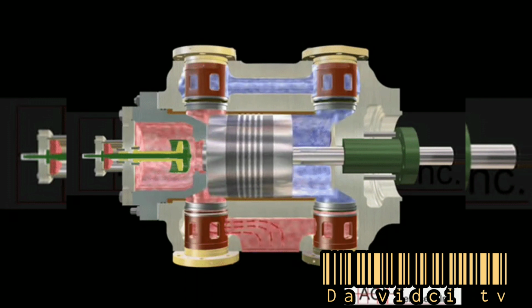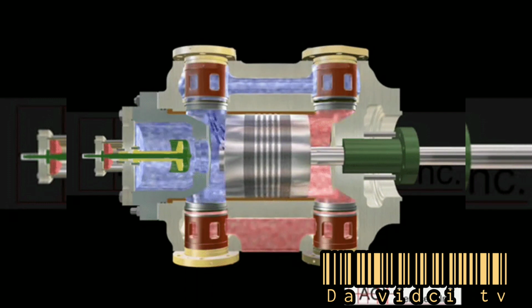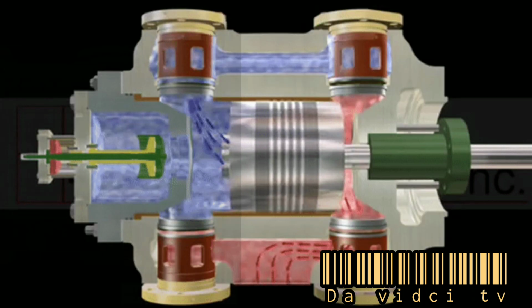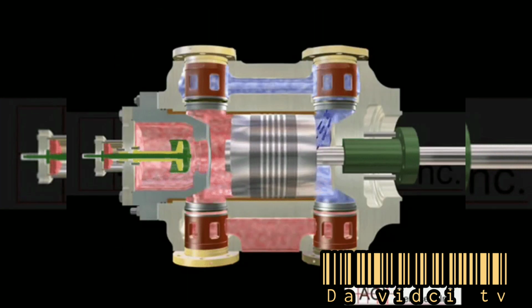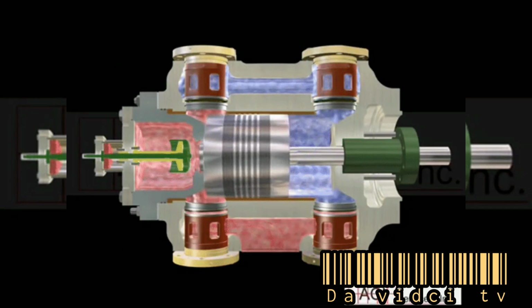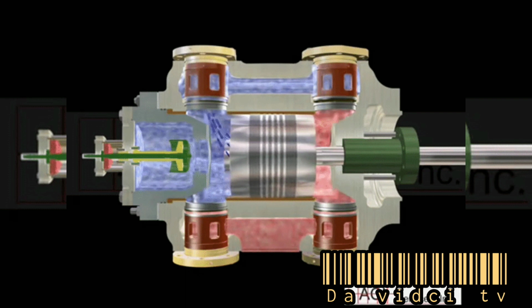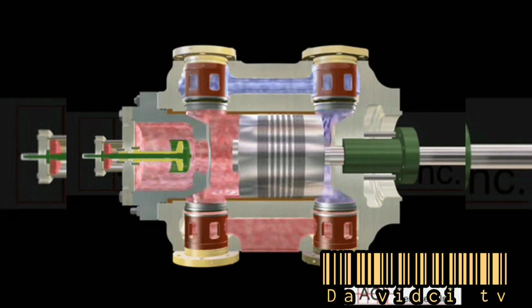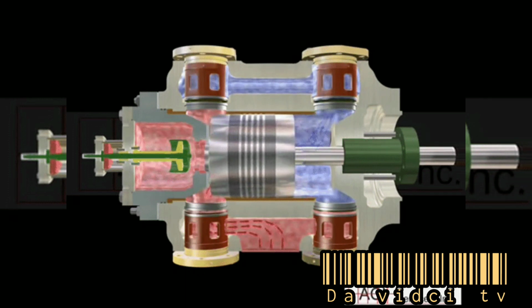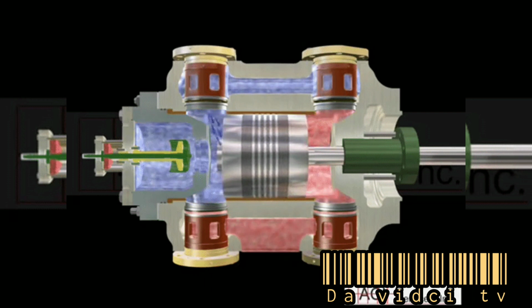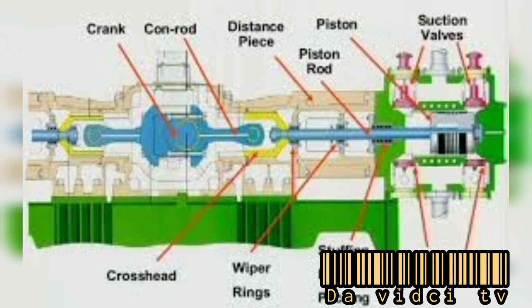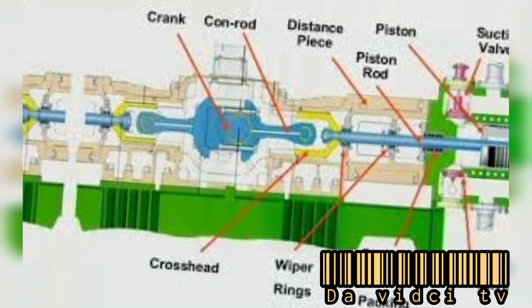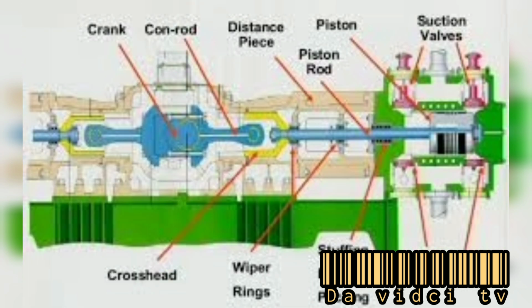If such a compressor has an integral electric motor sharing a common shaft with the compressor, it is called an engine type. These compressors can also be directly coupled to a separate electric motor in a more conventional manner. Gear units may be involved in the drivetrain where speed matching is required. Multiple frames are sometimes used with a common crankshaft in a compound arrangement to use a common driver.